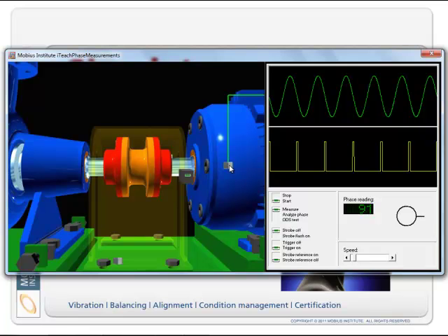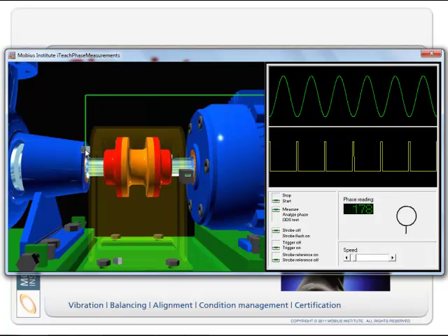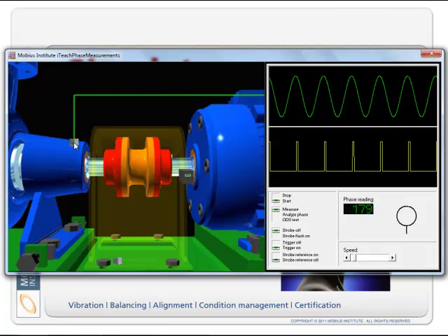We get that rotating vibration, and so if we move the sensor 90 degrees, we expect the phase to change 90 degrees. But I can do other things, like I can put the vibration sensor here, and then put it over here and see how the vibration changes. Okay, so here it's about 180 degrees, and here it's about 0 degrees, thereabouts. So I can see a 180 degrees phase shift. And yes, I am compensating for the fact that one face is pointing to my left and one face is pointing to my right.